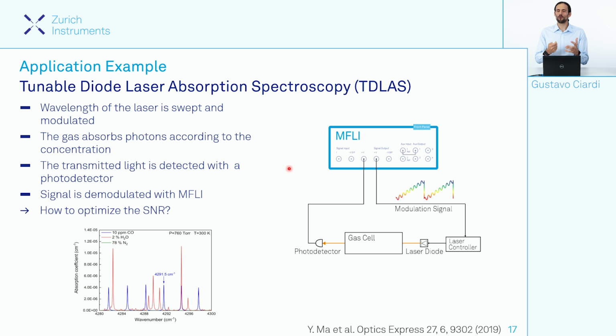TDLAS is one of the most common techniques used to analyze the properties of gases, for example concentration, temperature, flow velocity, or other parameters. This is usually done by measuring the wavelength-dependent absorption of light through the gas medium. As the name already suggests, it employs a tunable source, a laser diode, whose wavelength can be swept depending on the driving signal that we apply to it.